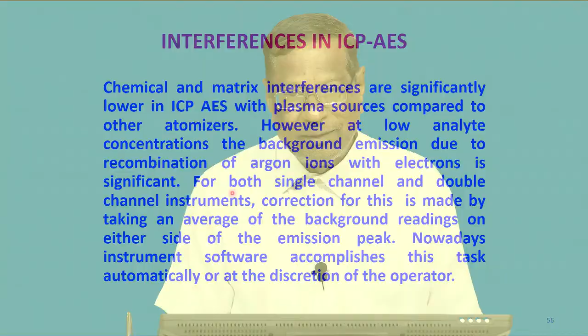So, for both single channel and double channel instruments, correction for the background is very important. That means, whatever is the background, you have to subtract it from the actual analyte signal, that is what we mean. So, background correction is a very important part of ICP AES. Nowadays, instrument software does accomplish this task automatically at the discretion of the operator. Sometimes the operator's ingenuity also helps in sorting out some of the problems.